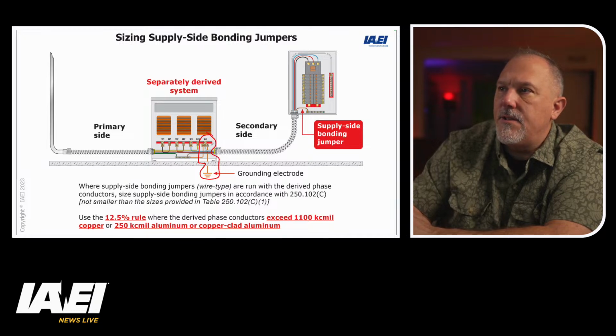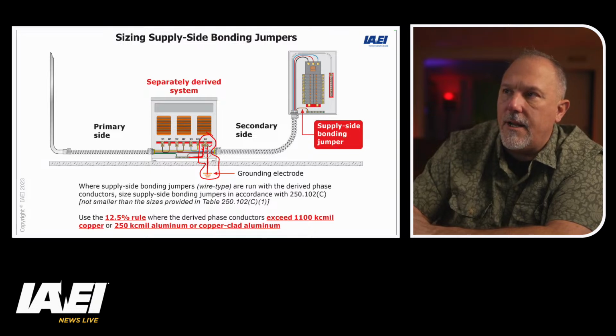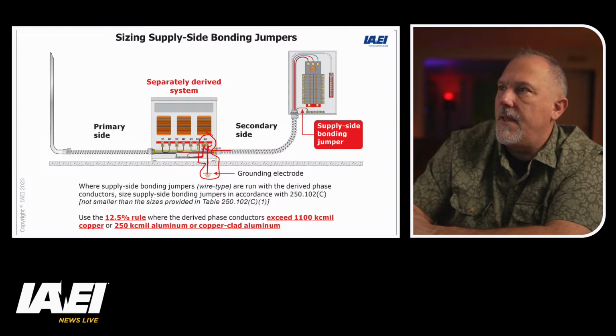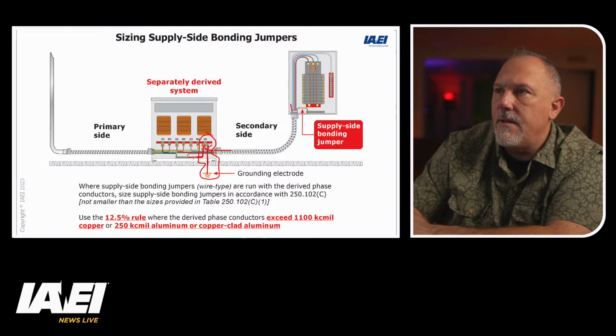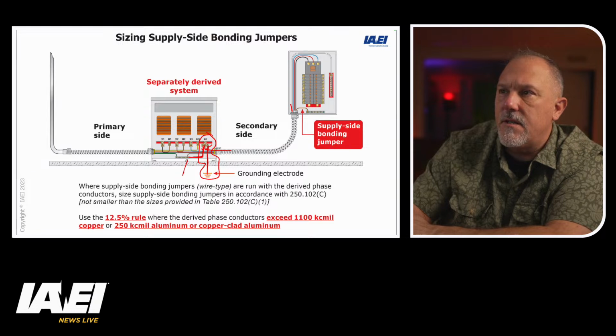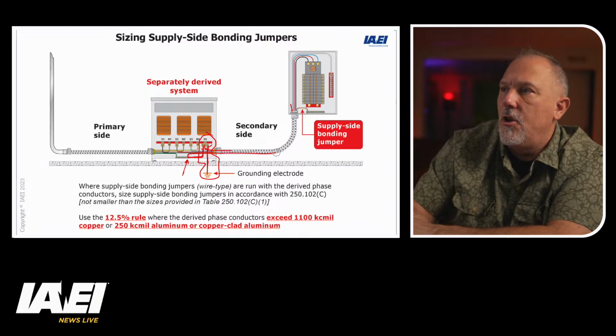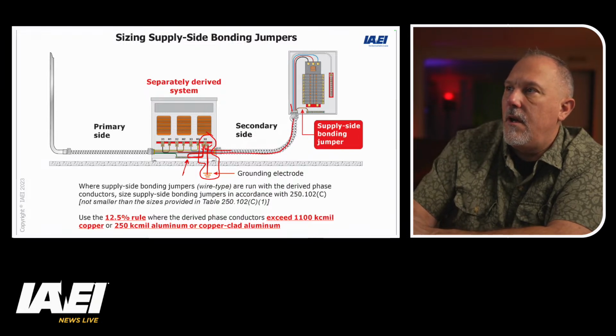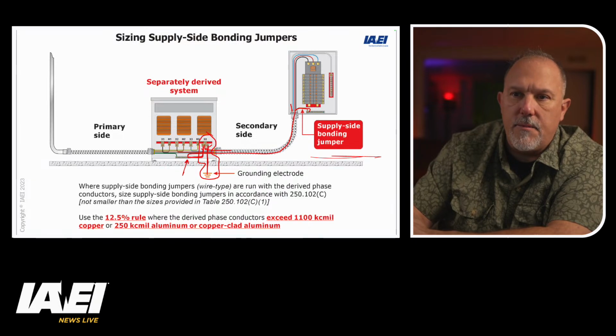That XO has 1, 2, 3 connections to it. So one of those connections bonds it here. One of those connections is connected to the grounding electrode. And then the other connection is this one that goes to there. And then from this terminal, I've got that bare copper conductor that goes through this, up, and connects there, and that's your supply side bonding jumper.